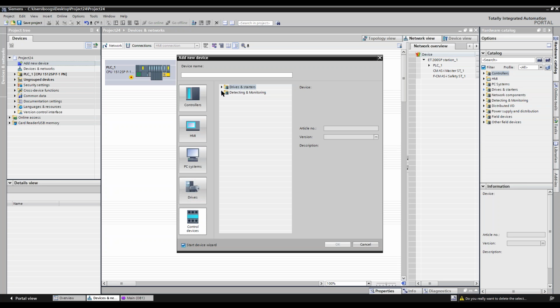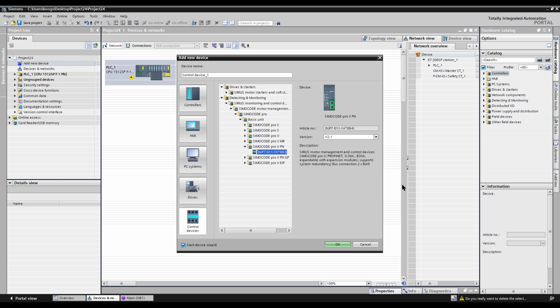Now notice I said that I can go in here and I can communicate with my soft starters, and I can do that with Simocode under Control devices. So now I'm going to go in. Go down to Simocode pro, basic unit, and then again, here's the different SIMOCODEs that we have. There's Ethernet IP, Profinet general purpose, Profinet, which is the high performance or high feature, Modbus RTU, and then Pro-V, this one's Profibus, this one's Profinet. So I'm going to pick Profinet.